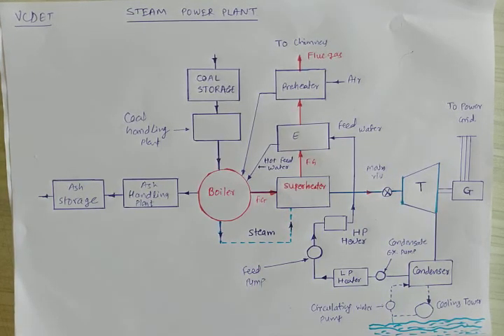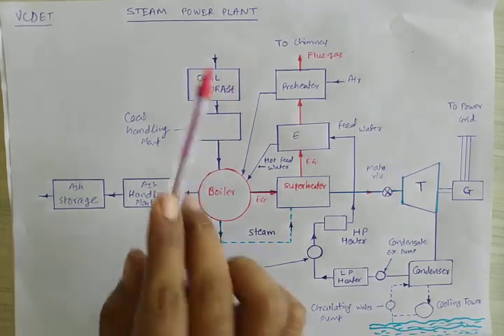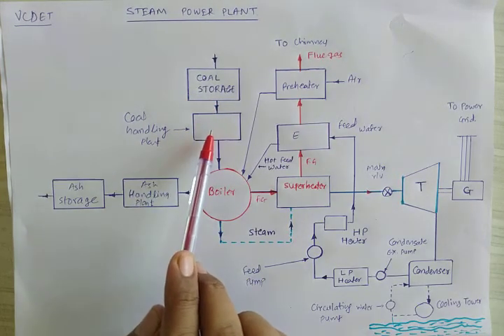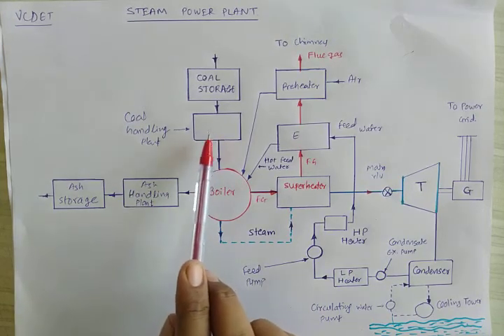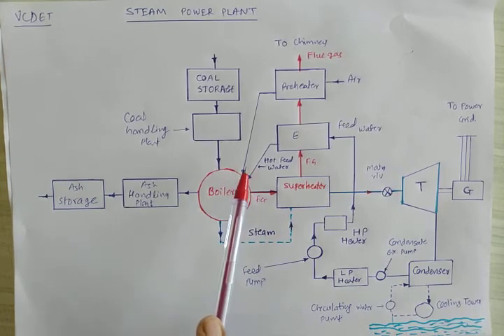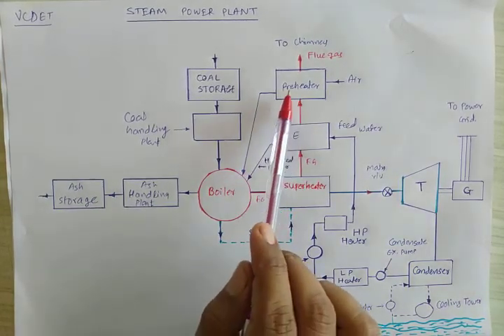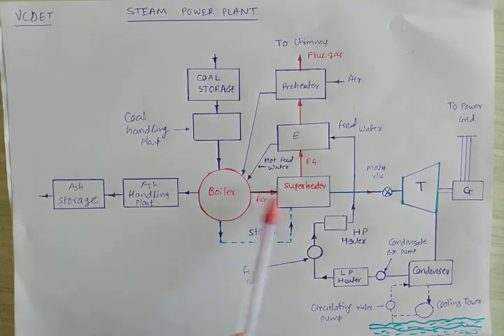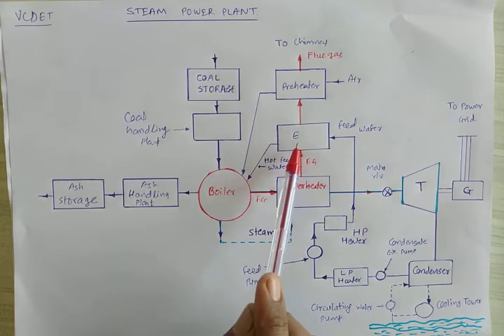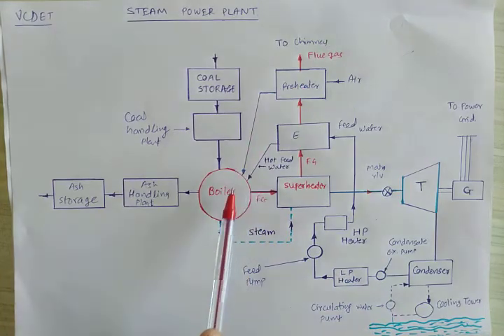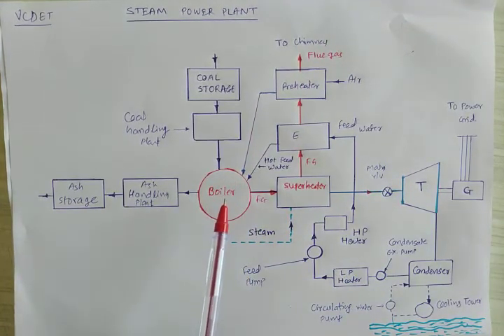In the modern thermal power plant, coal from the mines comes into coal storage, then is forwarded to the coal handling plant, and then into the combustion chamber of the boiler. At the same time, pre-heated air comes from the pre-heater. The flue gases leaving the boiler pass through the super-heater, then the economizer, and then the air pre-heater, where they pre-heat the incoming atmospheric air. That pre-heated air is sent back to the combustion chamber of the boiler for burning the coal.